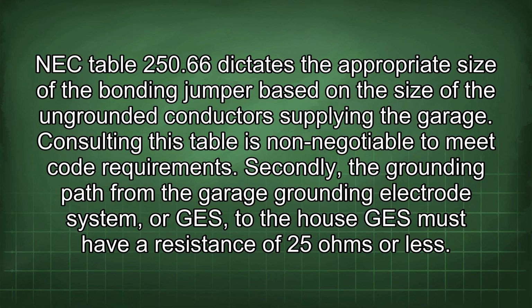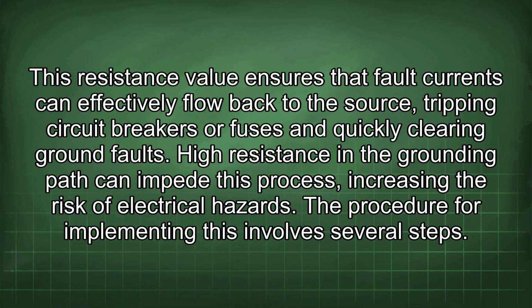Secondly, the grounding path from the garage grounding electrode system, or GES, to the house GES must have a resistance of 25 ohms or less. This resistance value ensures that fault currents can effectively flow back to the source, tripping circuit breakers or fuses and quickly clearing ground faults. High resistance in the grounding path can impede this process, increasing the risk of electrical hazards.